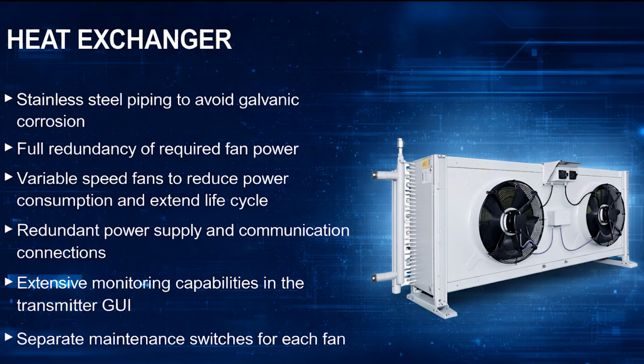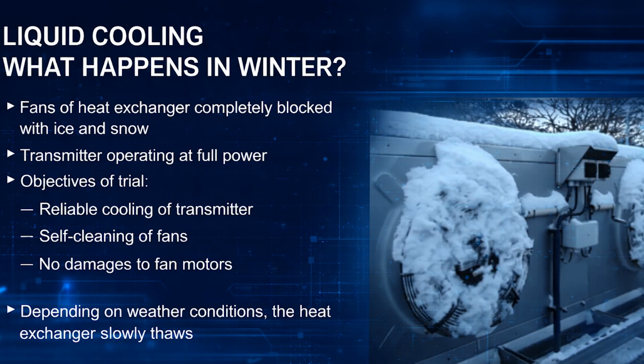From there, the coolant moves to the stainless steel heat exchanger outside, and this is where redundancy becomes critical. Redundant pumps, redundant fans, redundant cabling. Each pump and fan can carry the full thermal load on its own, and both operate with intelligent speed control to reduce energy consumption by more than 50% when full capacity isn't required. For sites in northern climates, liquid cooling performs flawlessly. Even in deep winter, hundreds of deployments prove this, and Rohde and Schwarz has validated this performance through full ice block testing of the cooling fans.